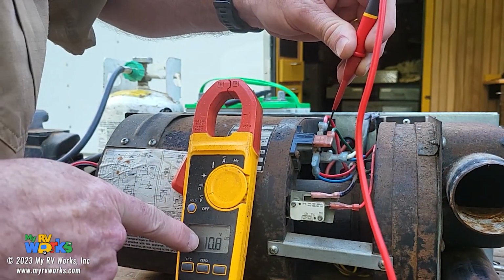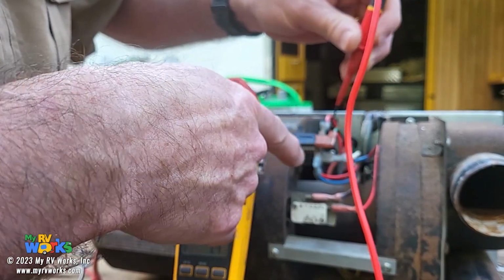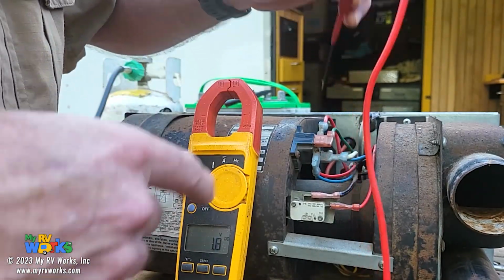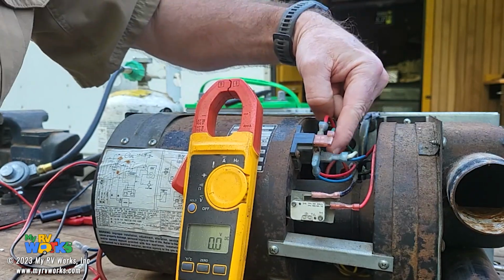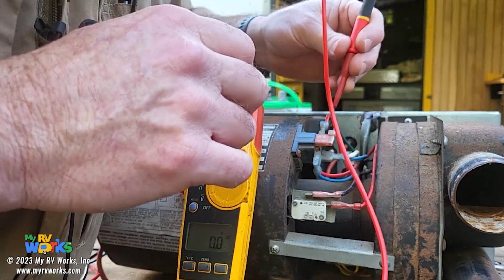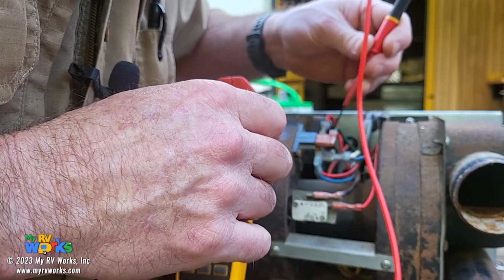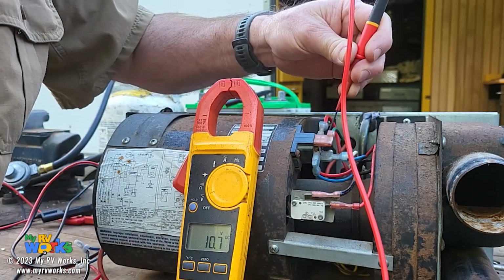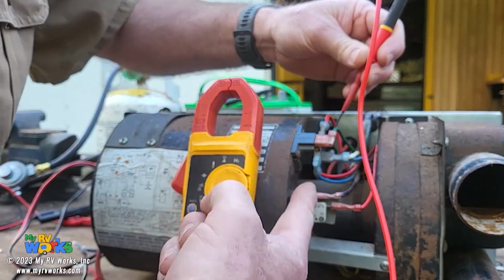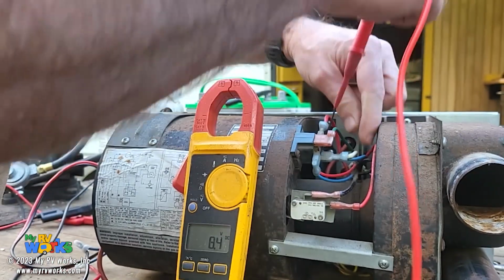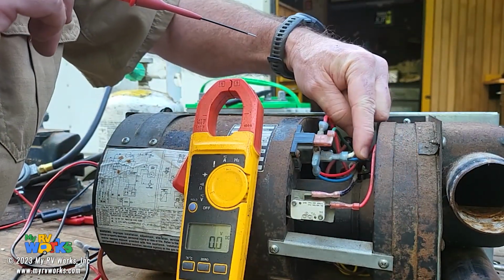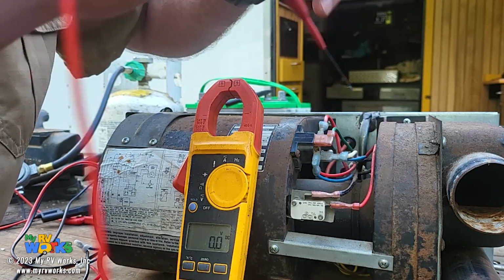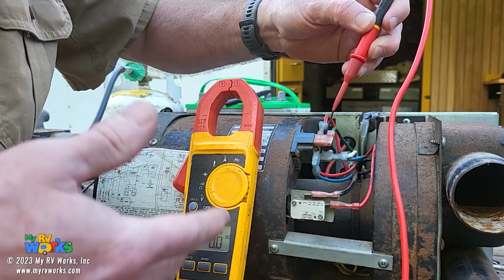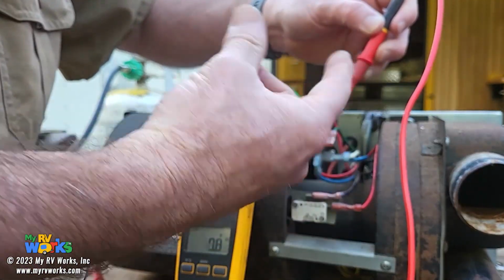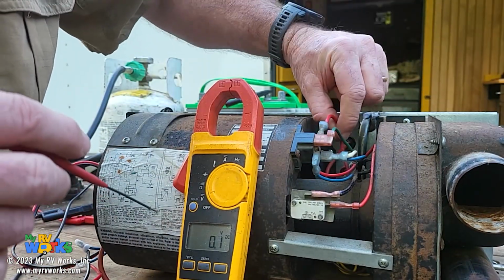I do, okay? So there's still a call for heat, and this furnace isn't smart enough to know that there's no flame to keep running. The problem is this relay here is still being told to run the fan. Let me get it in there again. Right there. And that was why I was going through all this stuff earlier, because there's still power on this blue wire coming back from the thermostat. As long as there's power coming on this blue wire back from the thermostat, I am energizing the coil of my relay. My relay is still being closed. It's still allowing the power to pass through to my motor.